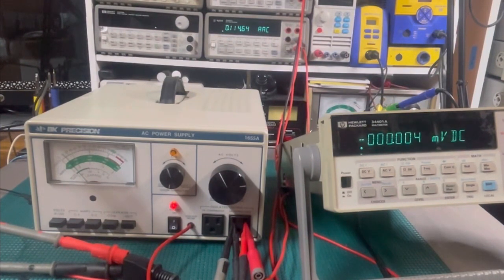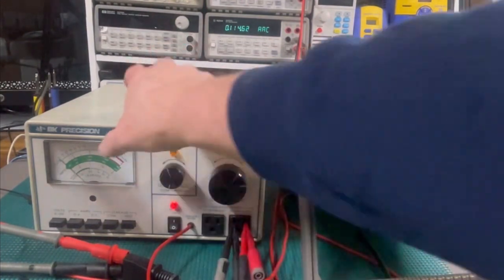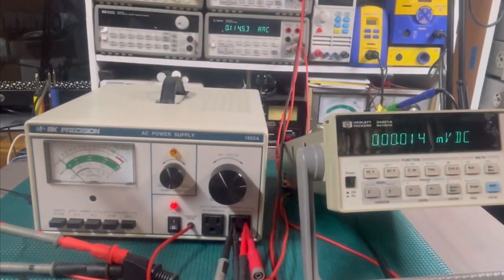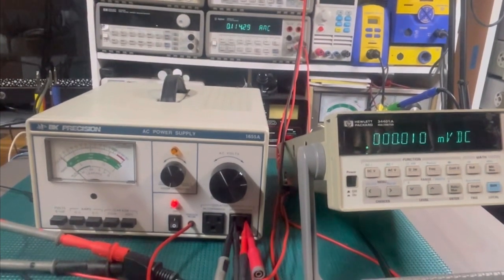But still, it's saying here on this gauge 500 microamps. You'd have to look at the specifications of the equipment you're testing. But I mean 100 microamps is virtually nothing. If that's accurate. We'll have to see. Again, going back to the amps, let me get something in here that'll actually draw some current, and we'll see what the Agilent thinks about the amperage gauge on the BK Precision.